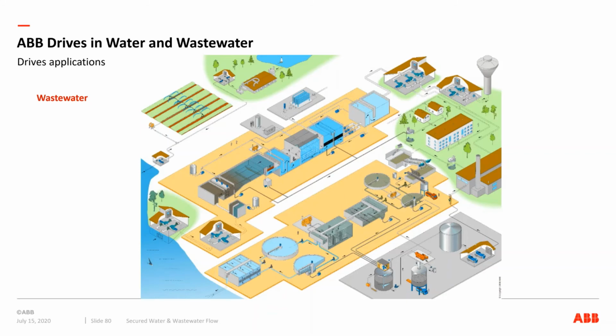Mike showed us the power bill showing the demand charge and the power factor. Putting a variable frequency drive on a motor helps increase the power factor. It also helps reduce your demand charge, because over a 15-minute period, you're going to use less energy because you're not running the pump at full speed and putting a valve on it or throttling it down. You're actually using it at the speed it needs to run to maintain constant pressure or constant flow or constant DO or constant level, whatever it is you're trying to accomplish with your installation there. Yeah, I think I've covered everything here.